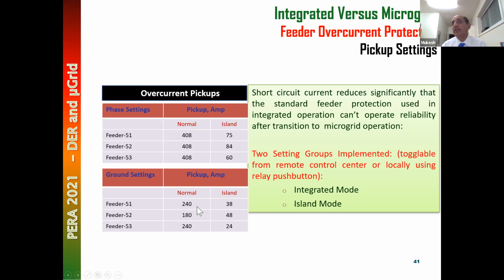Likewise, grounding. In a normal mode, we use 240 ampere. These are our standard settings. In a microgrid mode, we have used a much more sensitive setting. So we can toggle between the two groups of settings. This is the advantage of microprocessor-based relays. You can change settings through a simple control command. A control command coming from SCADA changes a group from a less sensitive to a more sensitive setting.